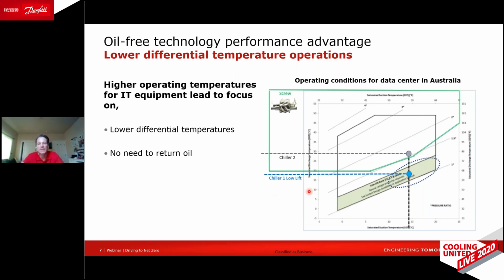And this is highlighting that. What you see on the right-hand side here is the operating map, with the suction temperature or the evaporator coming into the compressor on the low side, and the discharge temperature or the condensing side on the high side on the vertical axis. The combination of those drives the pressure ratio, which is the dotted line here. And what you see is that with screw compressors or other positive displacement compressors, where you have oil moving through the system and you have to return that oil back to the compressor, it is that differential pressure that drives the return of the oil. If you have no oil, with an oil-free system with Turbocor technology, then you have no oil to return, and therefore you can theoretically turn down further in terms of the pressure ratio, resulting in more efficient operation.